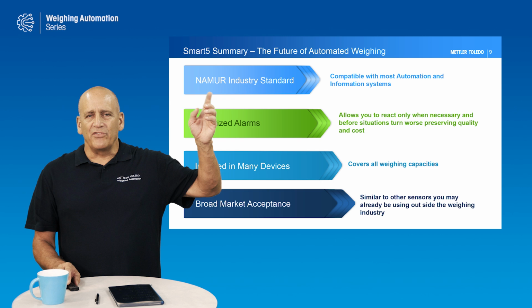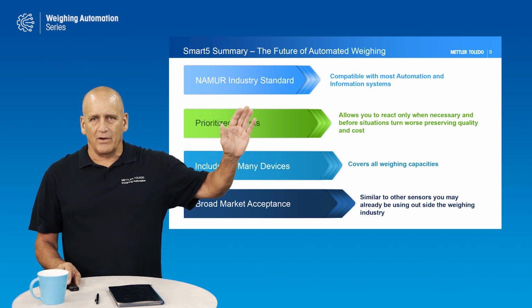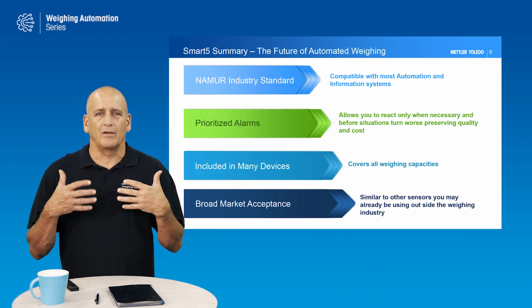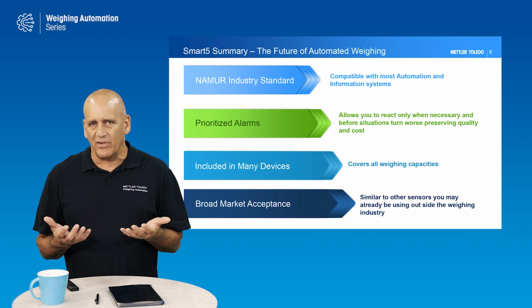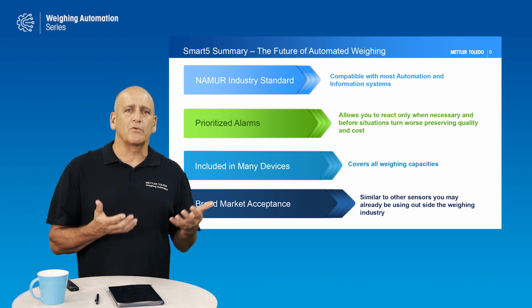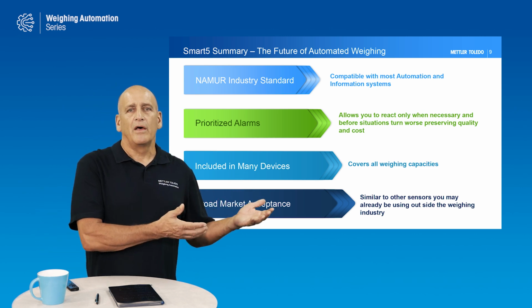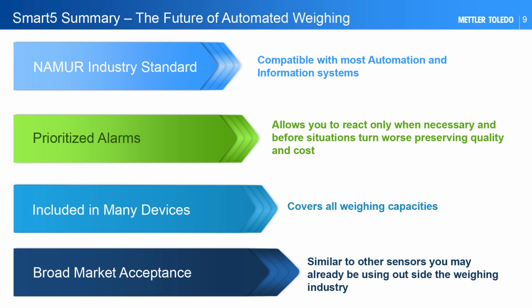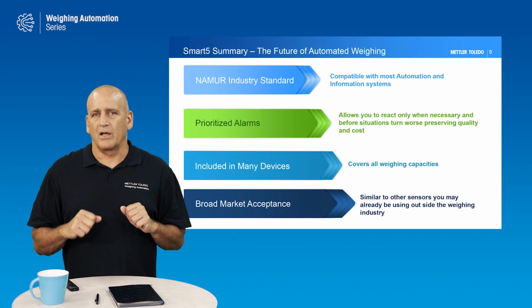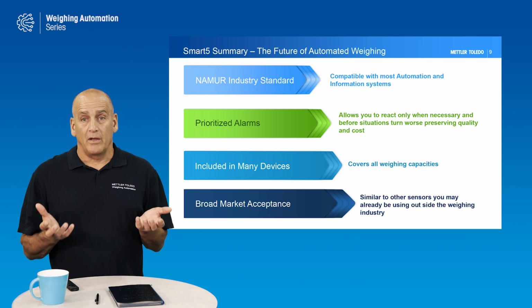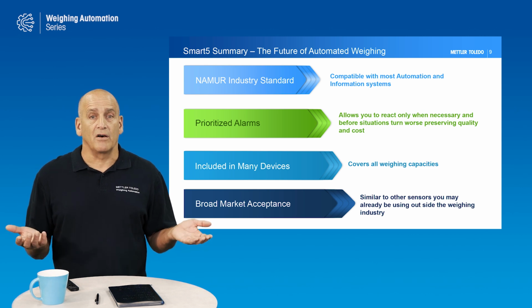So in summary, we're following the NAMUR industry standard. This is the top standard for alarming in our industry. This makes it compatible with all the automation systems. Automation systems from Rockwell and Emerson, Siemens, and so on, they're using these in their PLCs, DCS systems. These alarms have priorities, so that allows you to make decisions based on the priority level. It just doesn't alarm all the time. It just gives you a lot of noise or an alarm flood. It basically lets you decide for yourself.